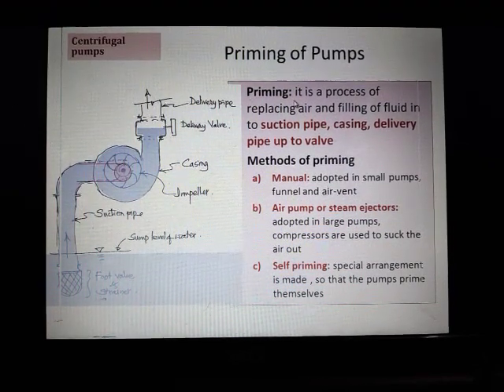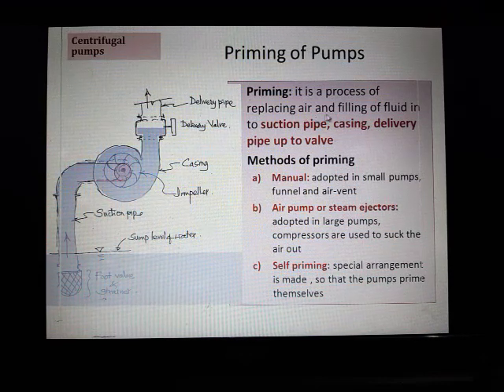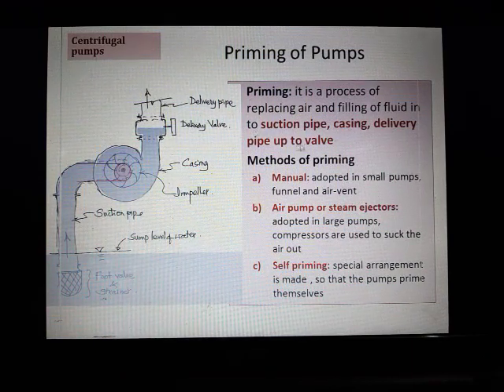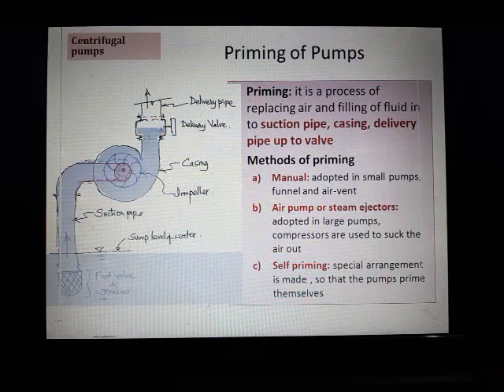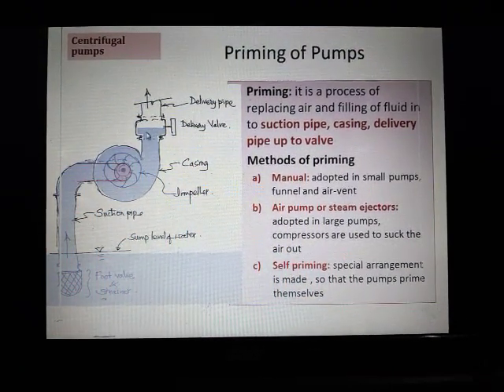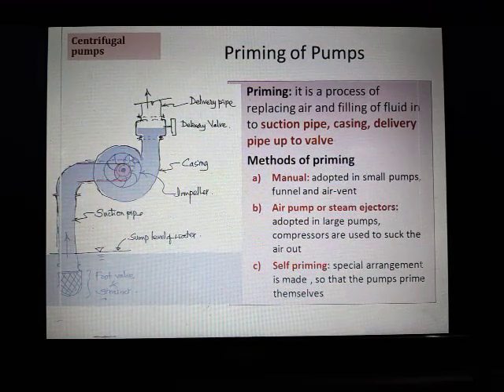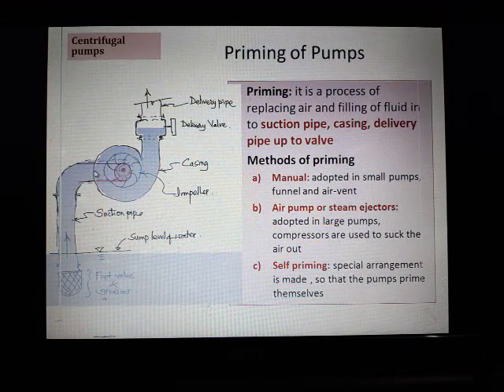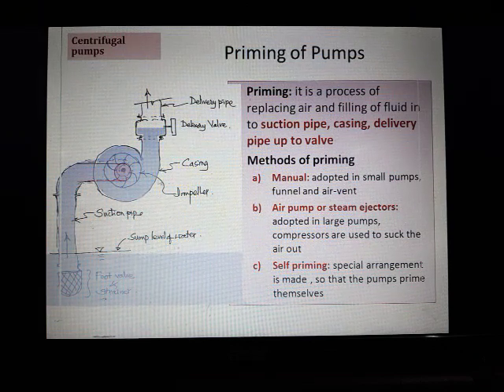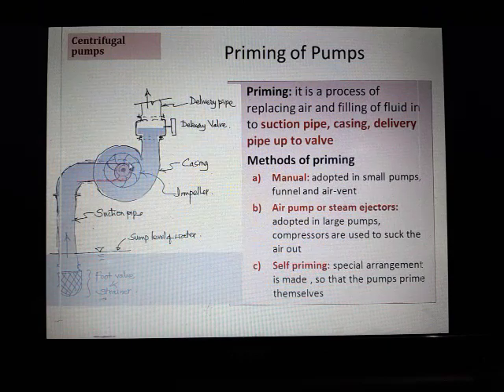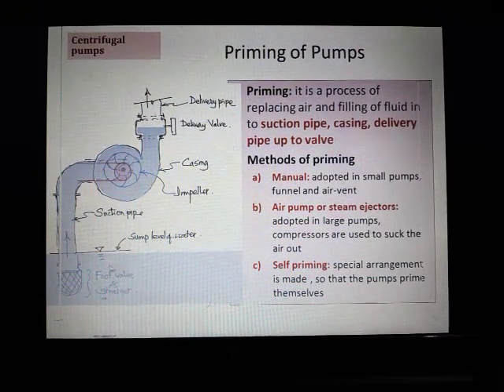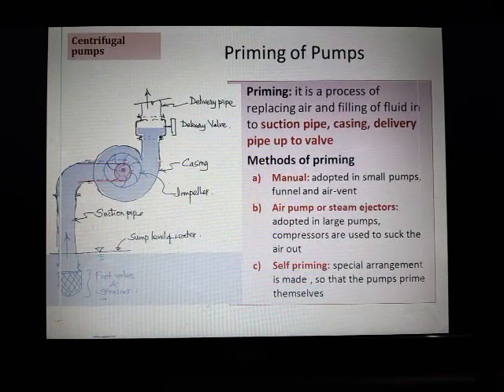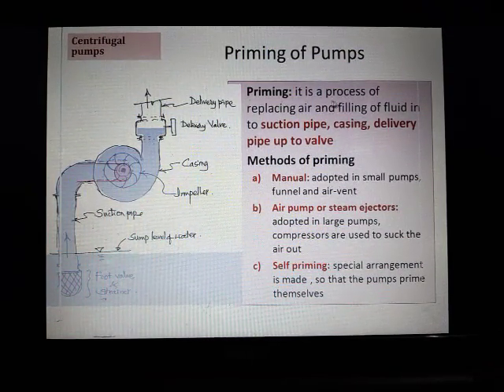Priming is a process of replacing air and filling fluid or liquid into the suction pipe, casing, and delivery pipe up to the valve. In the beginning there will be air inside; you have to fill this space with the liquid you want to pump. That is known as priming — unless the filling is done you will not be able to start pumping. So priming is essential.